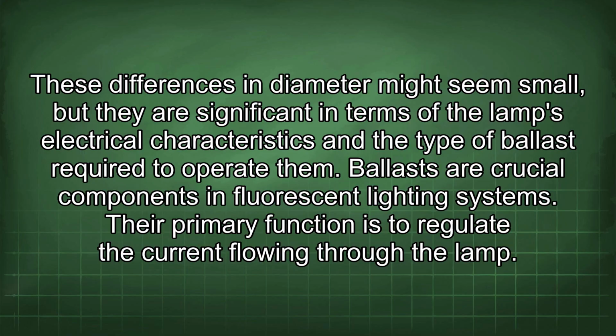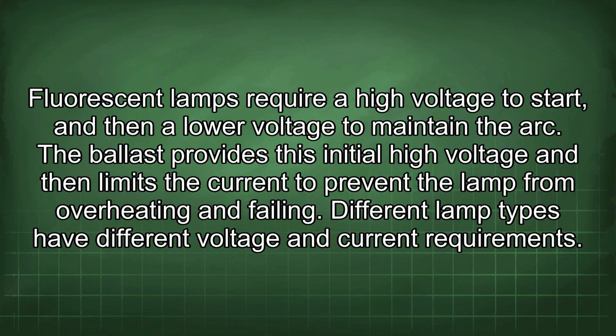Ballasts are crucial components in fluorescent lighting systems. Their primary function is to regulate the current flowing through the lamp. Fluorescent lamps require a high voltage to start, and then a lower voltage to maintain the arc. The ballast provides this initial high voltage and then limits the current to prevent the lamp from overheating and failing.